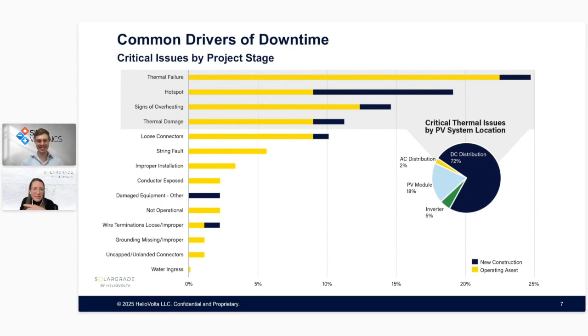Okay, well, let's dig a little deeper on those critical issues that always cause downtime now. So nearly 70% of them, and that's the top 4 issues highlighted at the top of the screen, are directly related to thermal anomalies. So when equipment temperatures are high, there's a risk of a thermal event or fire, and there is no incident with higher potential for downtime, lost revenue, reputational harm, and most importantly, safety risks than a fire. So de-energizing the system and sacrificing some energy yield is clearly worthwhile to avoid a catastrophic failure scenario.